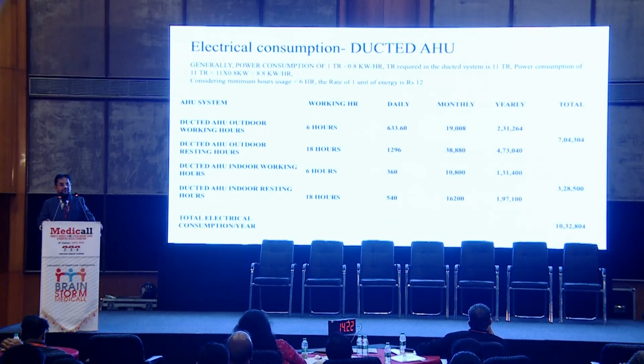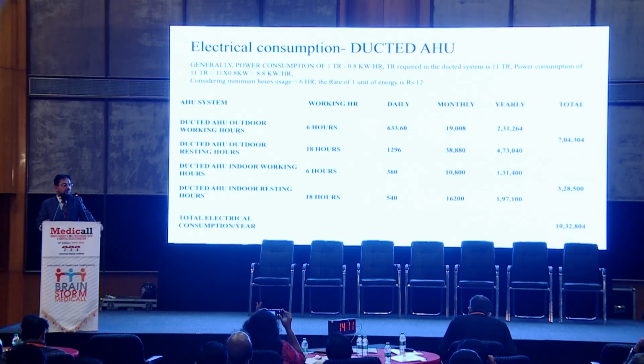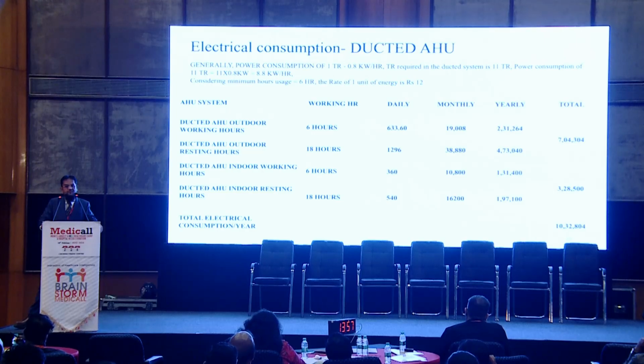Here is one small calculation I had given for the ducted systems. If I use the system for 6 hours in a day, 6 hours normally we use for the operation theater, then how much will be the electricity consumption in the working hours and the non-working hours? Because in the non-functioning hours, you have to maintain the flow. At that time, NABH suggests that you can increase the temperature a little, instead of 24 you can go up to 28, 29. And another thing is that you can run the fan at 50% efficiency.